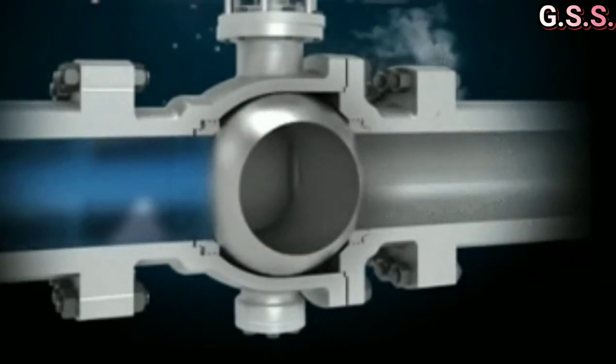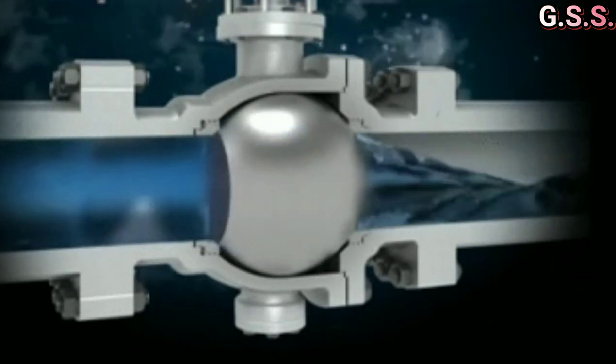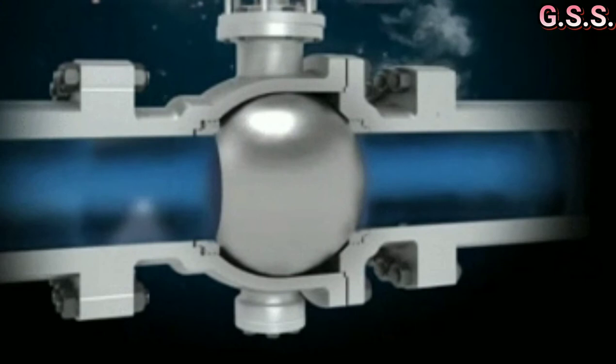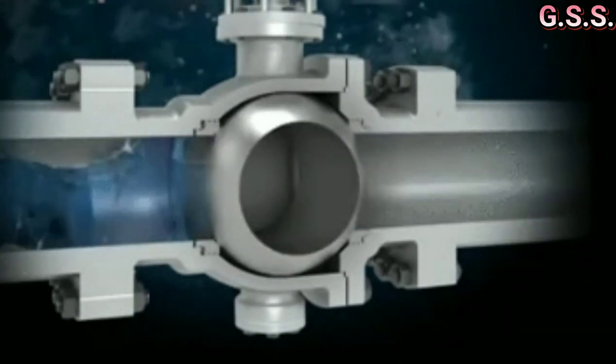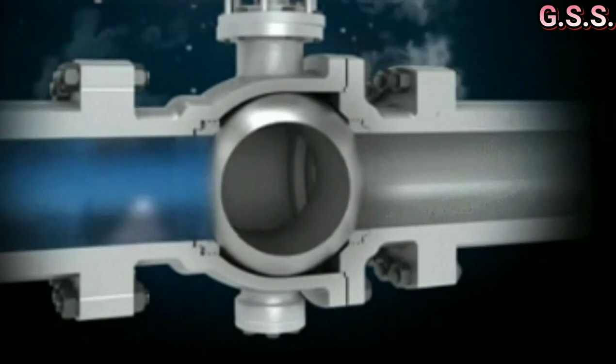Through a full bore ball valve, there is a straight flow path without any reduction of flow. Hence, pressure drop is less and debris or small particles can pass through the ball.